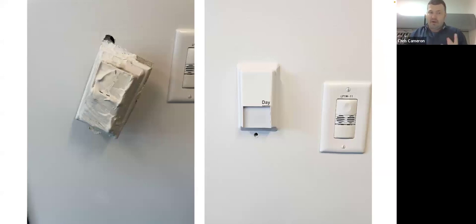This is a real picture from my facilities work: what happens to your thermostats is important because it relates to your collection space. A drywalling contractor mudded right over the thermostat — the before and after photos show the same space just a few days apart with the thermostat covered in drywall mud. We had to replace that sensor. In many spaces I've seen people just scrape some drywall off so the vents could see conditions and carry on — but to me, once that happens the thermostat is pretty much useless. What your sensors experience matters.